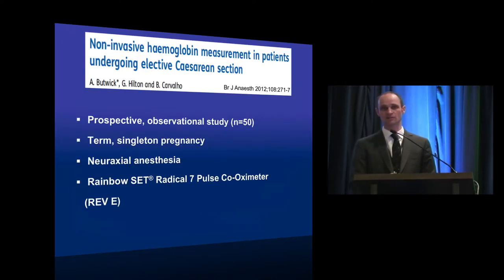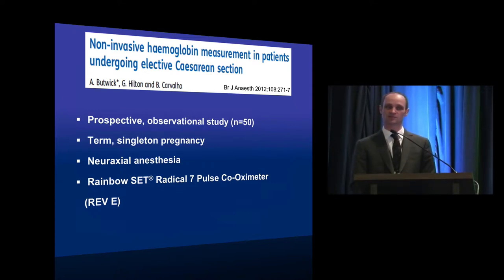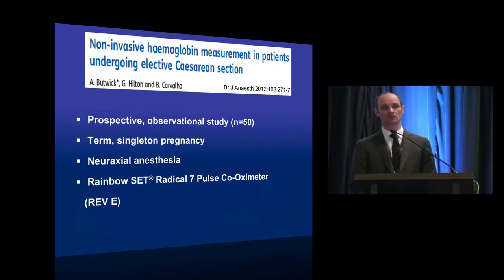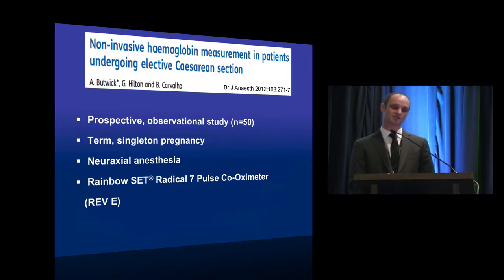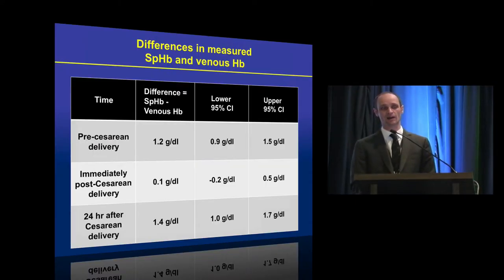Back in 2012, we published a study looking at device performance in a homogeneous cohort: healthy patients undergoing elective cesarean section with singleton pregnancies under spinal or combined spinal-epidural anesthesia. We compared device hemoglobin values to lab values at three time points — before C-section, immediately after in recovery, and 24 hours after delivery. The device appeared to overestimate the lab hemoglobin concentration both before C-section and at 24 hours, by at least one gram per deciliter, with considerable variability raising questions about precision.